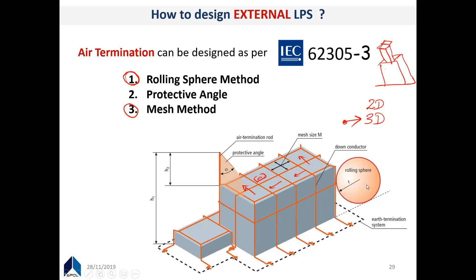You're going to roll a sphere and check what areas are affected and what areas require improvements. The other method is the protective angle method, which is more like a simplified version of the rolling sphere method. We'll look at these before going into a practical session. For the rolling sphere method, according to the classes we discussed from class 1 to 4, the sphere radius varies from 20 meters to 60 meters. For a class 1 system, you shall have a 20-meter radius sphere, and for a class 4 system, let's say this is a 60-meter radius.